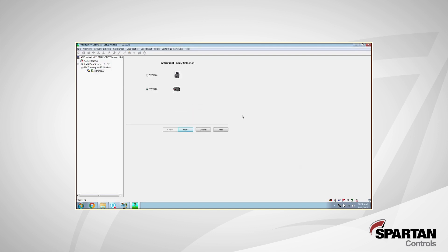With the DVC now out of service, it's going to ask us a series of questions about our assembly. First things first, depending on the generation of DVC you have, you may or may not see this question. It's asking us what type of DVC are we setting up here? Is it a 6200 or a 6000 series? The easiest way to tell would be to check the nameplate of your DVC or to simply just look at the connection head on your DVC. If it's on the left side, as you can see in this small picture here, it's a DVC 6200. And if it's on top, it's a DVC 6000 series. Us today, we have a 6200. So I'm going to click next.